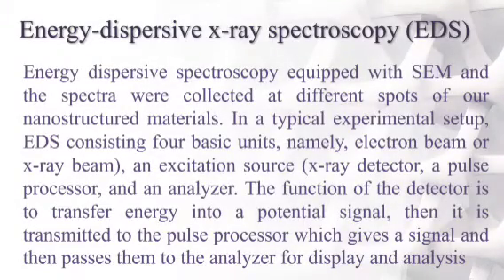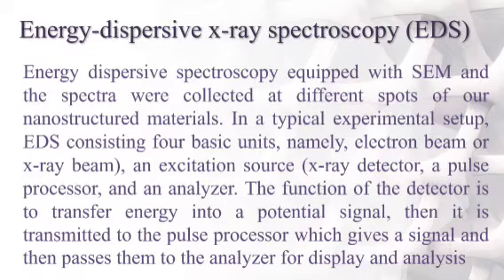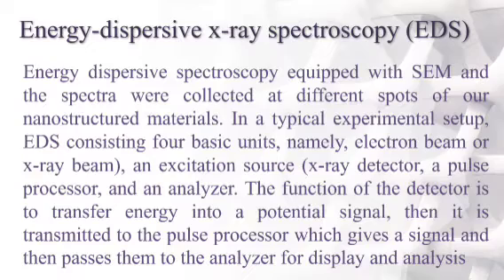Energy dispersive spectroscopy (EDS) is a common technique to identify the chemical constituents in a material, especially the presence of elements in a sample. EDS is equipped with SEM, and spectra were collected at different spots of the nanostructured materials. A typical EDS setup consists of four basic units: electron beam, excitation source, detector, and pulse processor, which sends the signal to the analyzer for display and analysis.